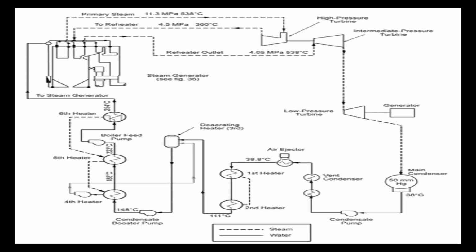Now, something is missing from this diagram, and that is certainly that there is no place indicated for make-up water to join the system. We will typically be recycling about 95% of our condensate, but we'll still need to make up small amounts with make-up water. Well, this would typically enter prior to the deaerator stage here.